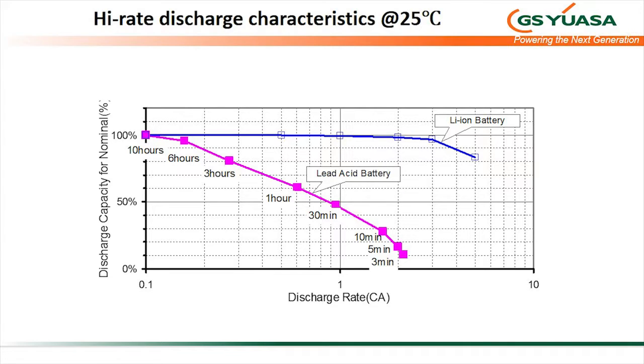By the time you're discharging it over a period of 30 minutes, you've only got about half of that ampere hours. So if you discharge at 100 amps, it will give you that 100 amps over 30 minutes, which is 50 ampere hours. So you've lost half the available capacity.